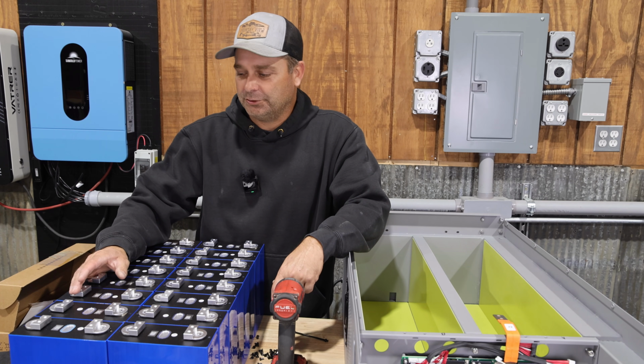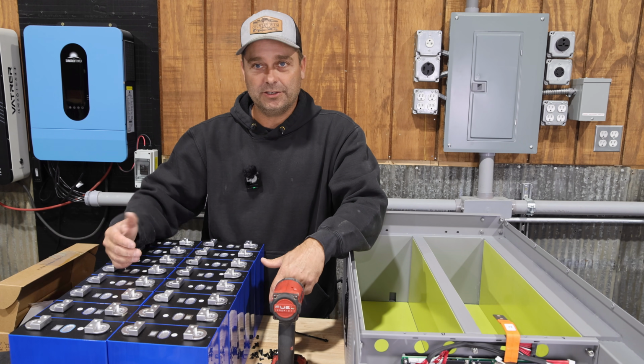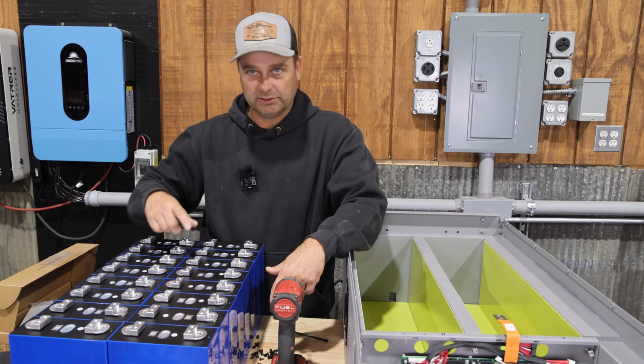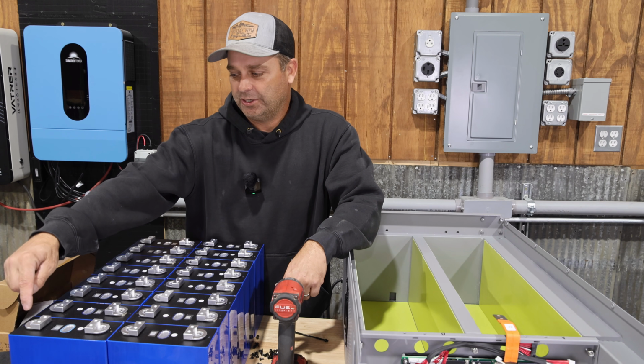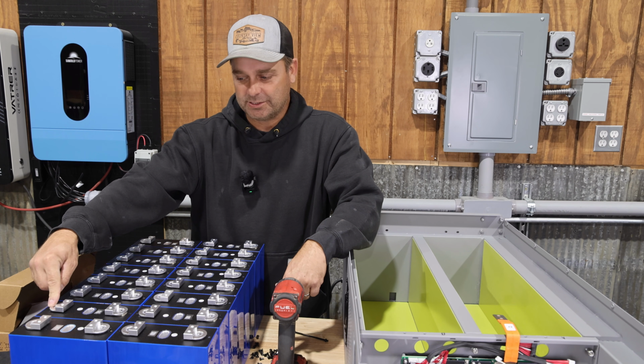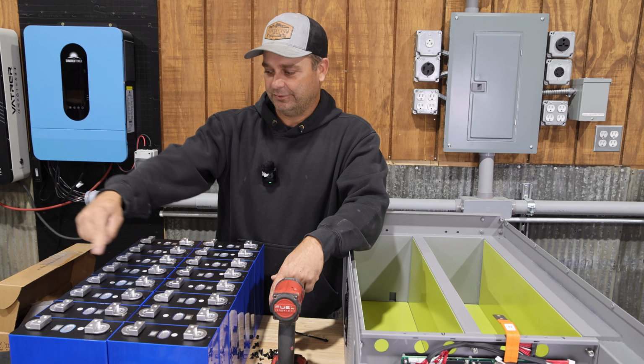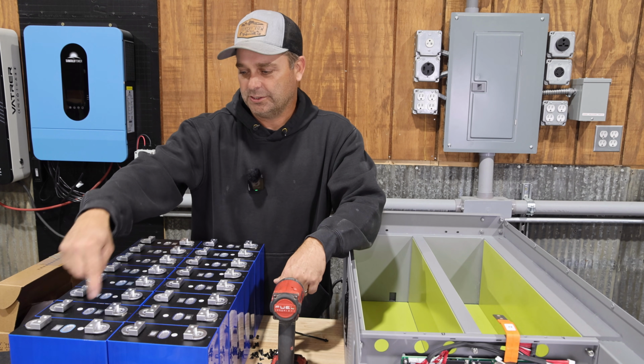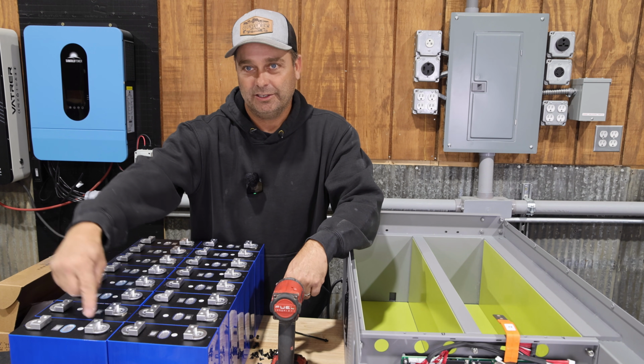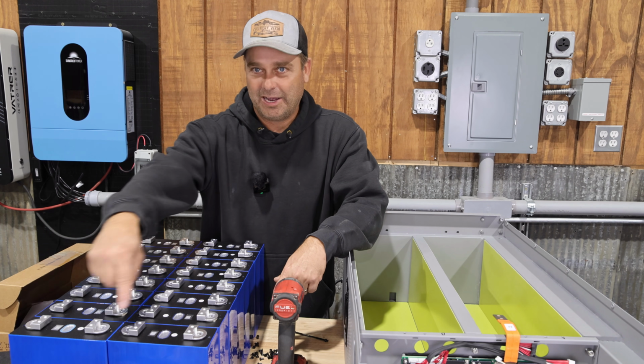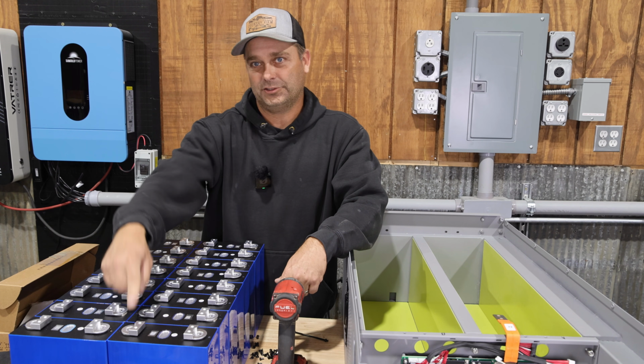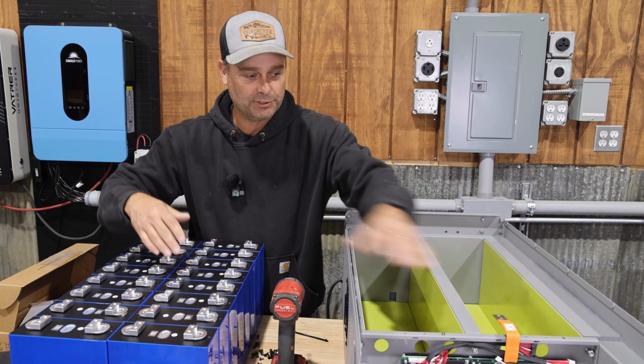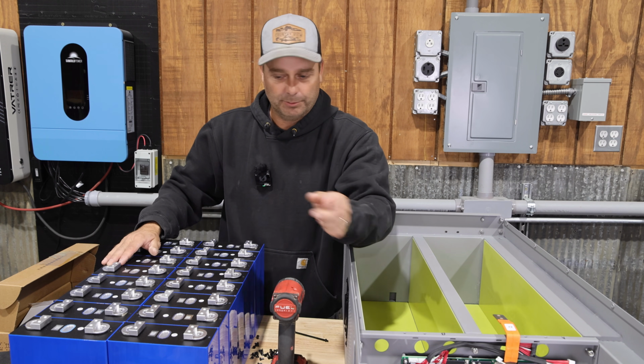The reason the batteries alternate is because we'll be hooking them up in series with little bus bars. It's going to make everything line up the way it should, so you end up connecting a negative to a positive, a negative to a positive, and so forth. When it's all in series, you'll have a positive terminal here, it'll go through the batteries in series, and end on a negative terminal on the other side. That's how those bus bars hook up to the BMS and to the breaker.